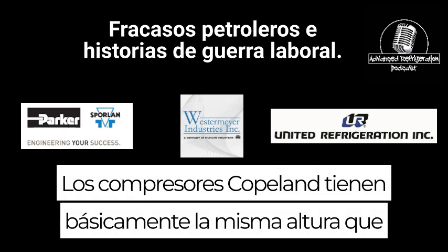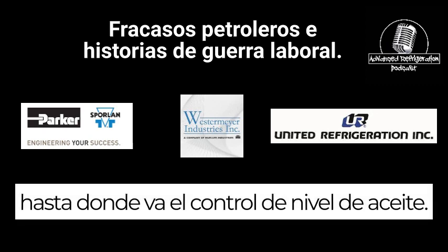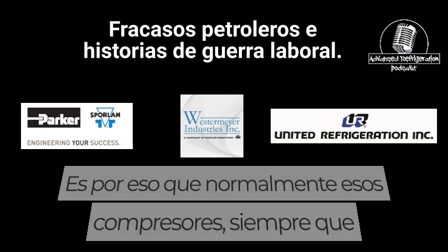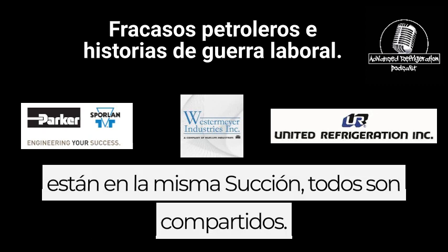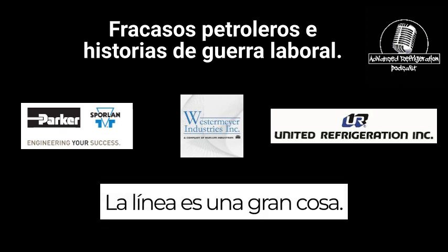Copeland compressors are basically all the same height as far as where the oil level control goes, so it's not as imperative. That's why typically those compressors, as long as they're on the same suction, are all shared. The purpose of the oil equalization line is a great thing.